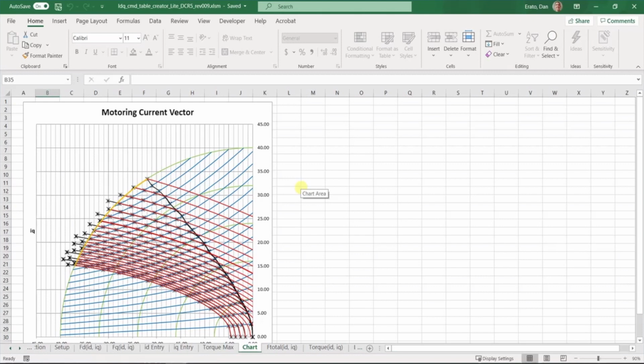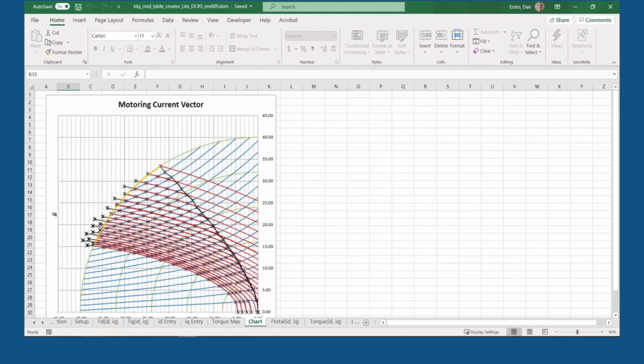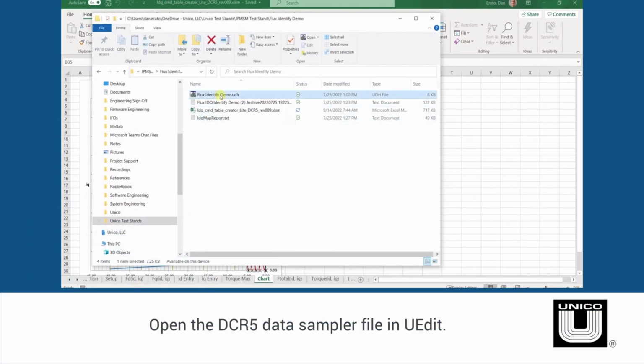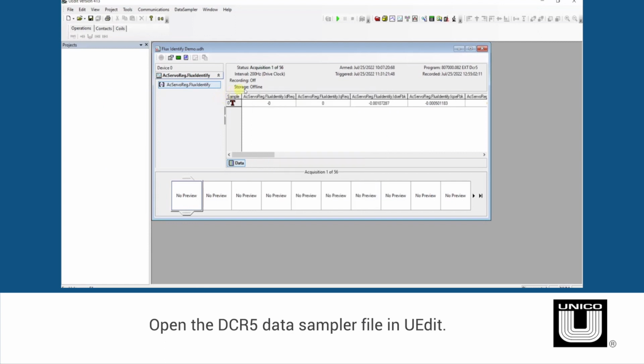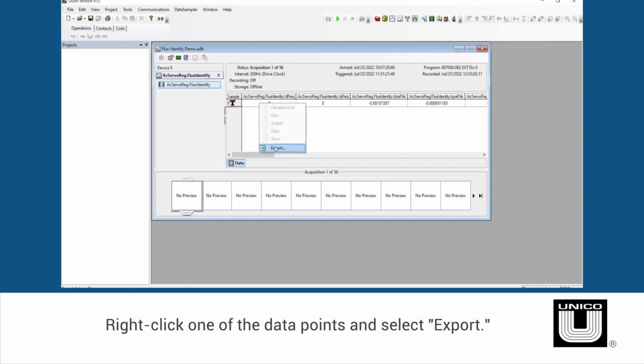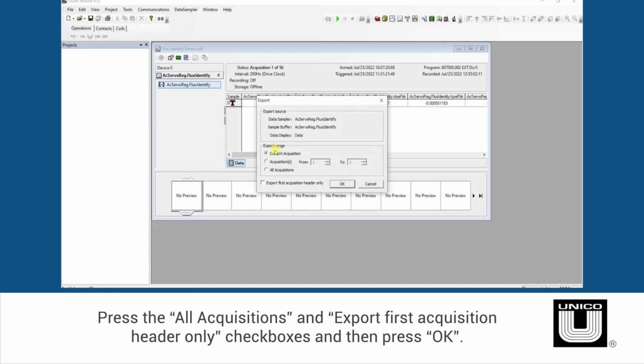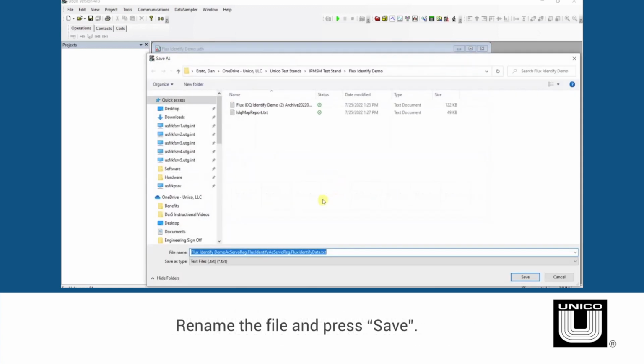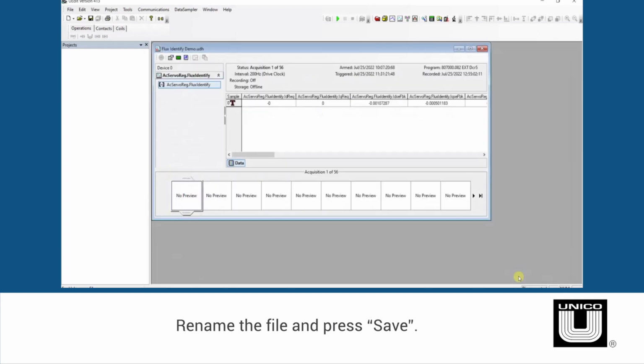An additional step in analyzing the data is to ensure there were negligible errors in the current and torque during the flux mapping process. So open the DCR5 data sampler file in UEdit. As you can see, I only have 56 samples as opposed to 374 because I skipped a portion of the flux mapping process. Regardless, right-click one of the data points and select Export. Select All Acquisitions to export all the data points. Also select the Export First Acquisition header only. Rename the file to something appropriate, and then select Save.